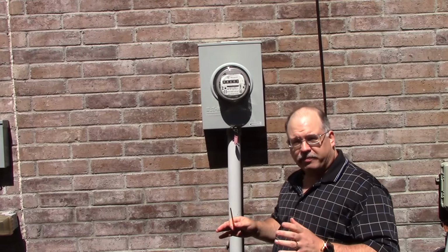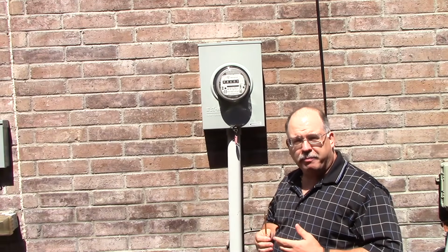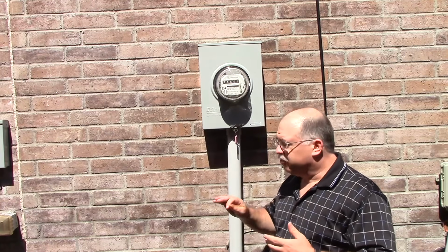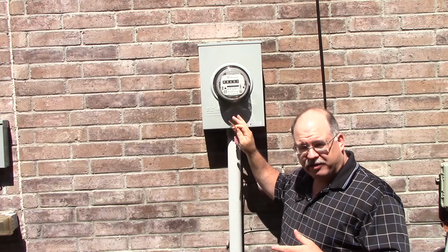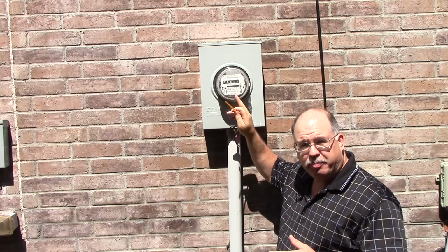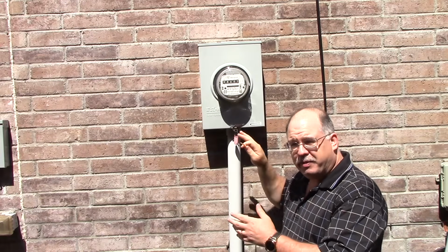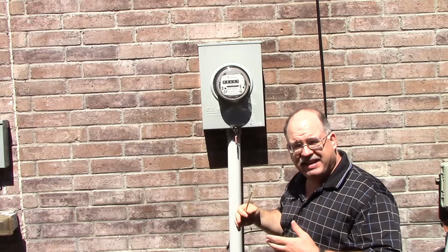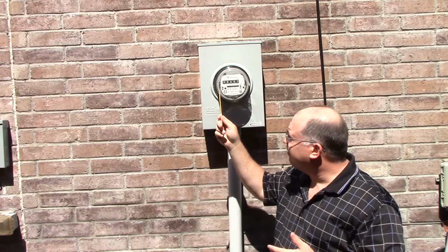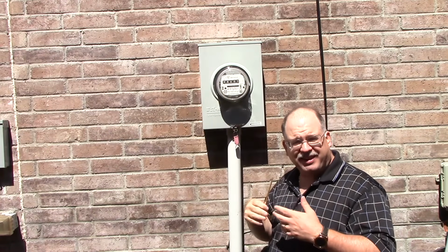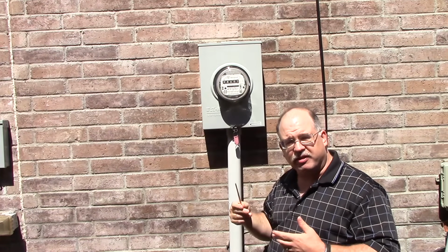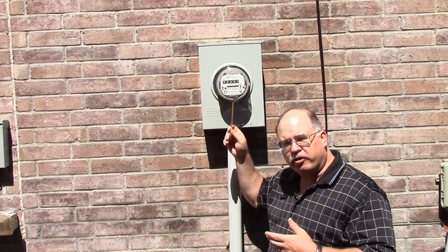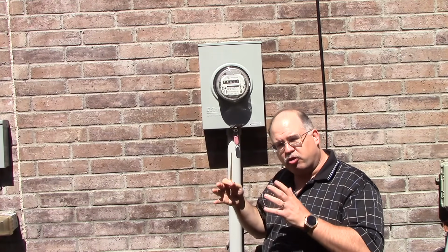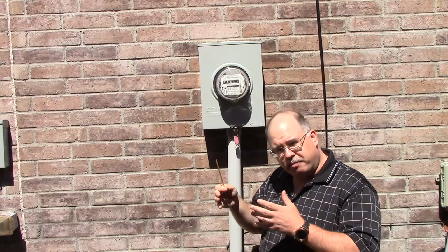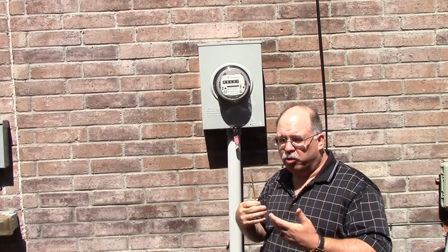Okay, we're out here at the meter. Now, one thing to remember about a meter when you're sizing a service is that you don't want to rely on it. Okay, sometimes they can take this meter socket and put it into different types of meter enclosures, and it might not be what you think it is. For example, this says CL200, which is very typical for a 200 amp service. However, I have seen CL200 meters installed in square 100 amp meter enclosures. So you don't want to rely on that.